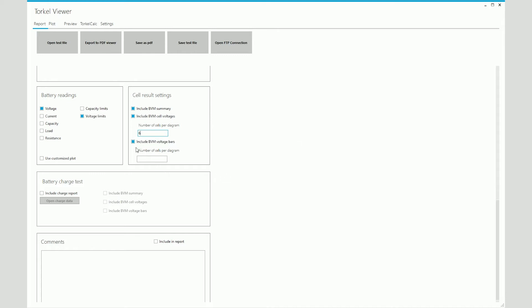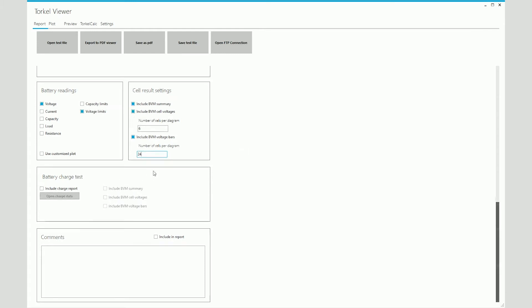And then finally, if you check this box, you'll be able to see the same information in the form of bar graphs. And in this case, you can have 24 bar graphs in one diagram. It shouldn't be too complicated. Now, if after stopping the discharge test, you continued monitoring the individual cell voltages while the battery was being charged back up, and you want to include that information in the report, then you can do that by checking this box.